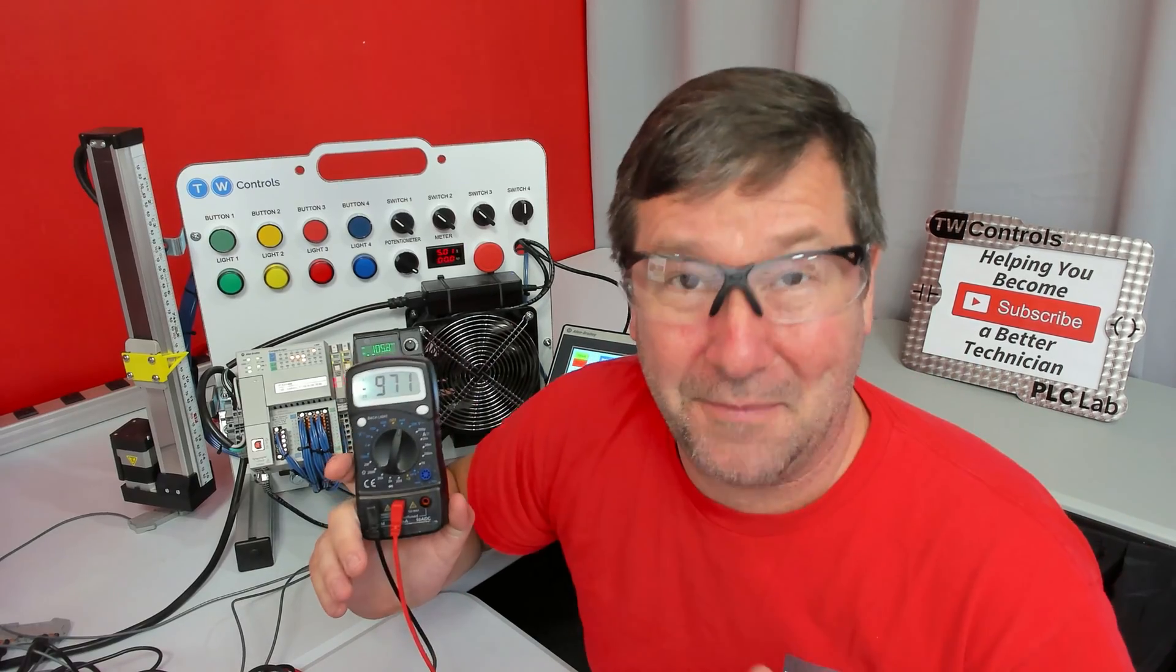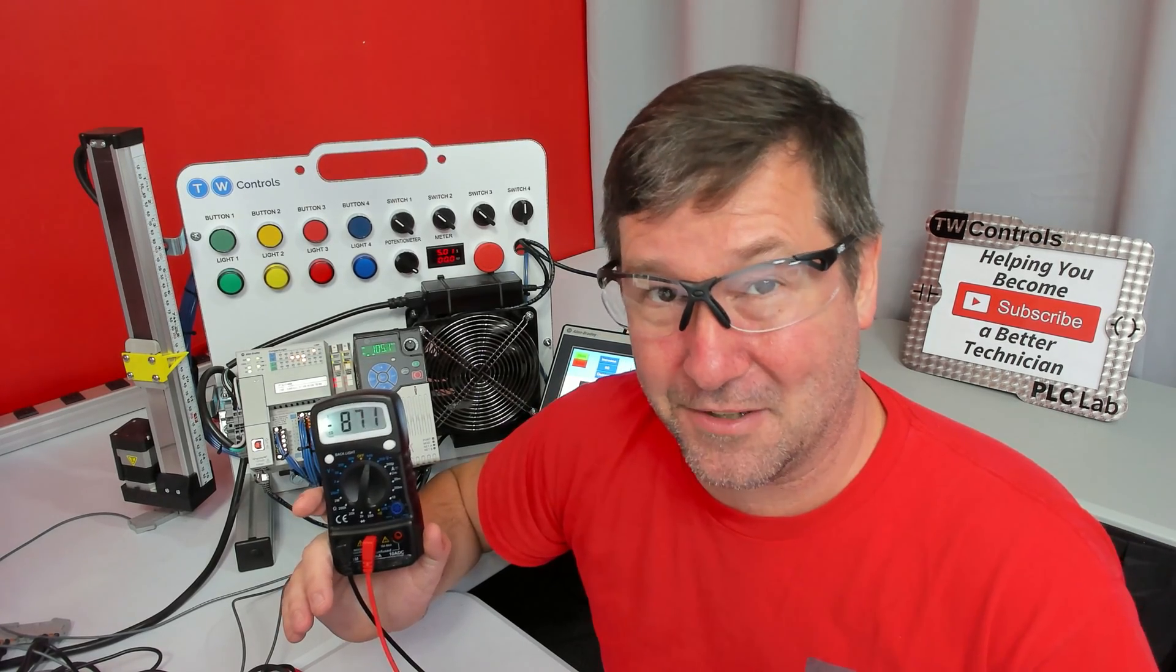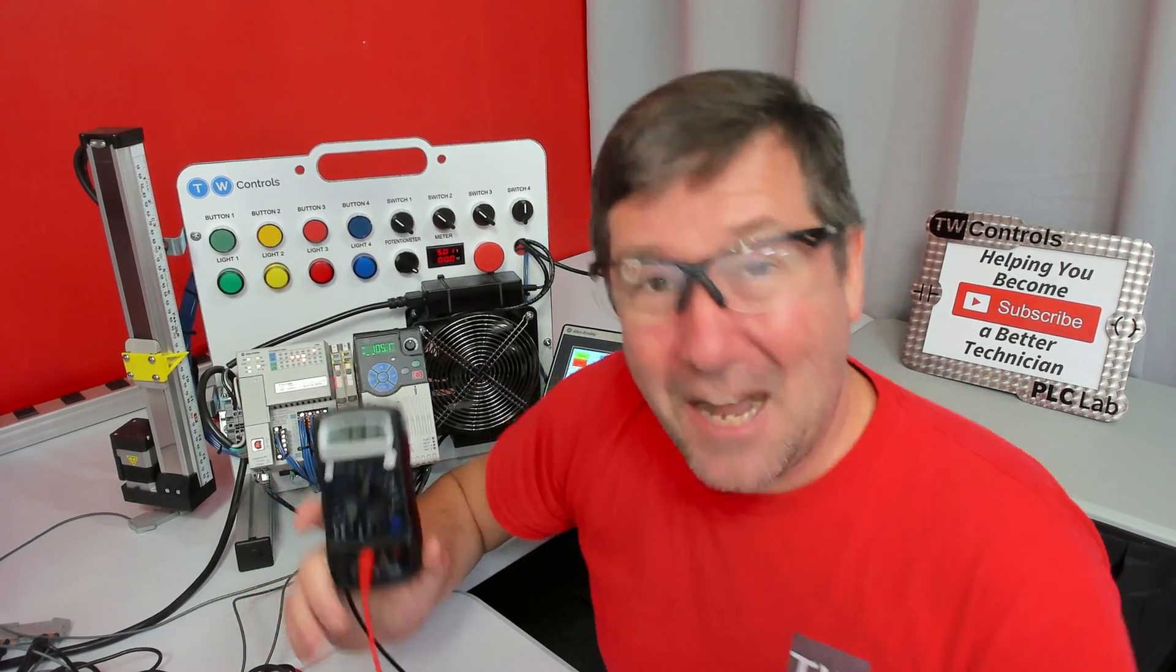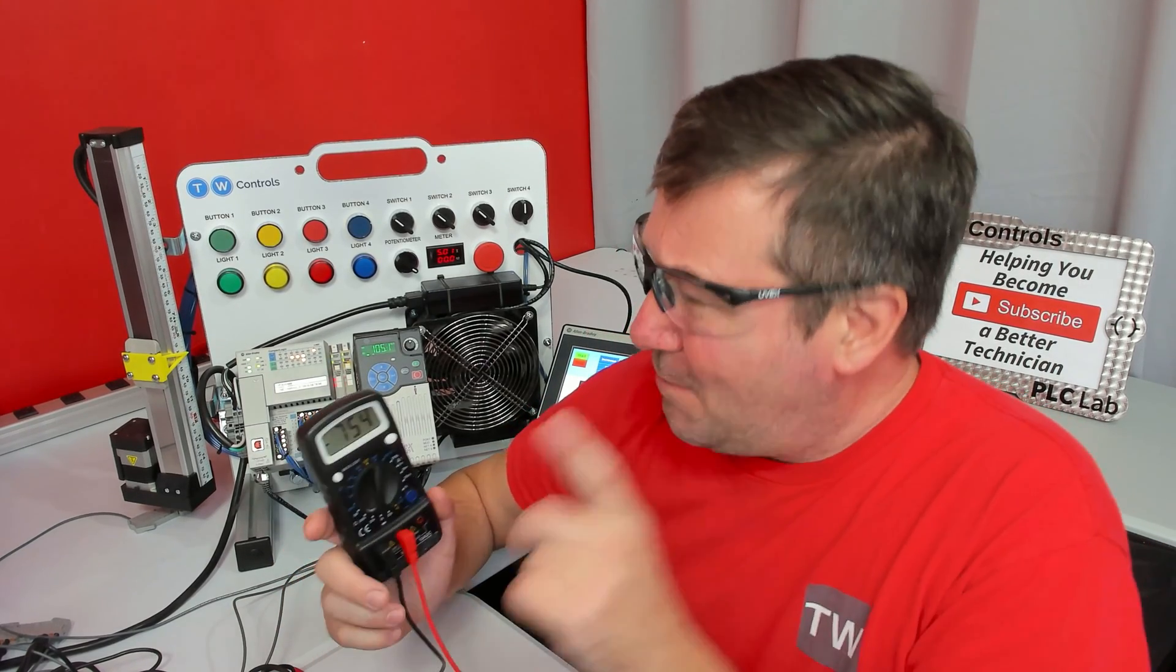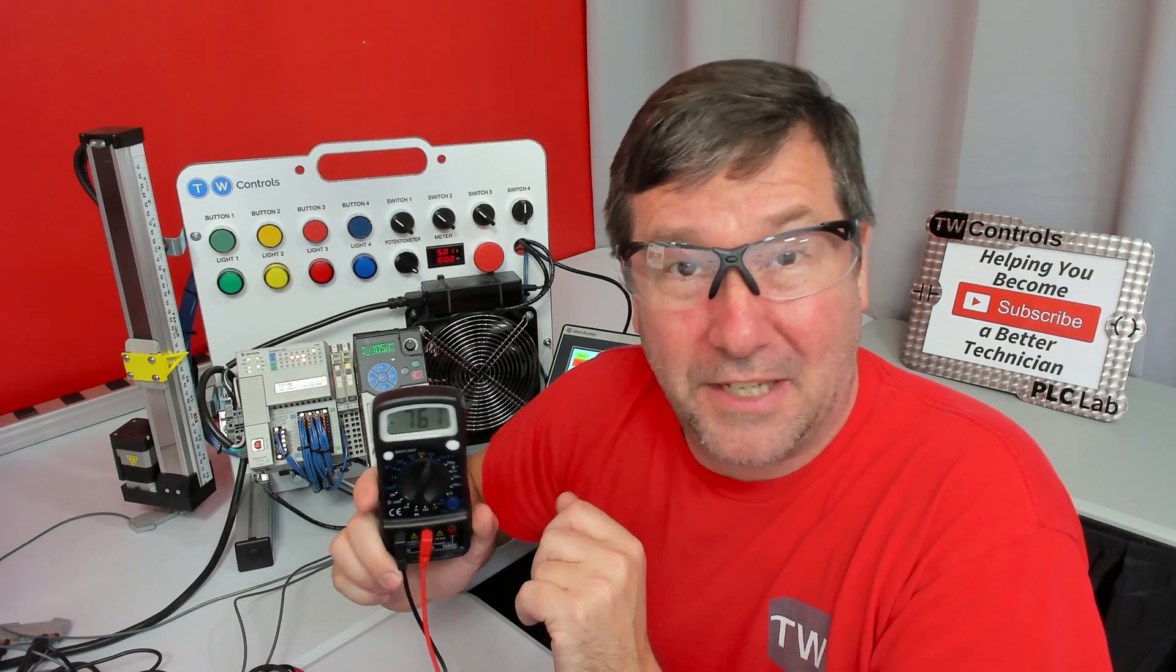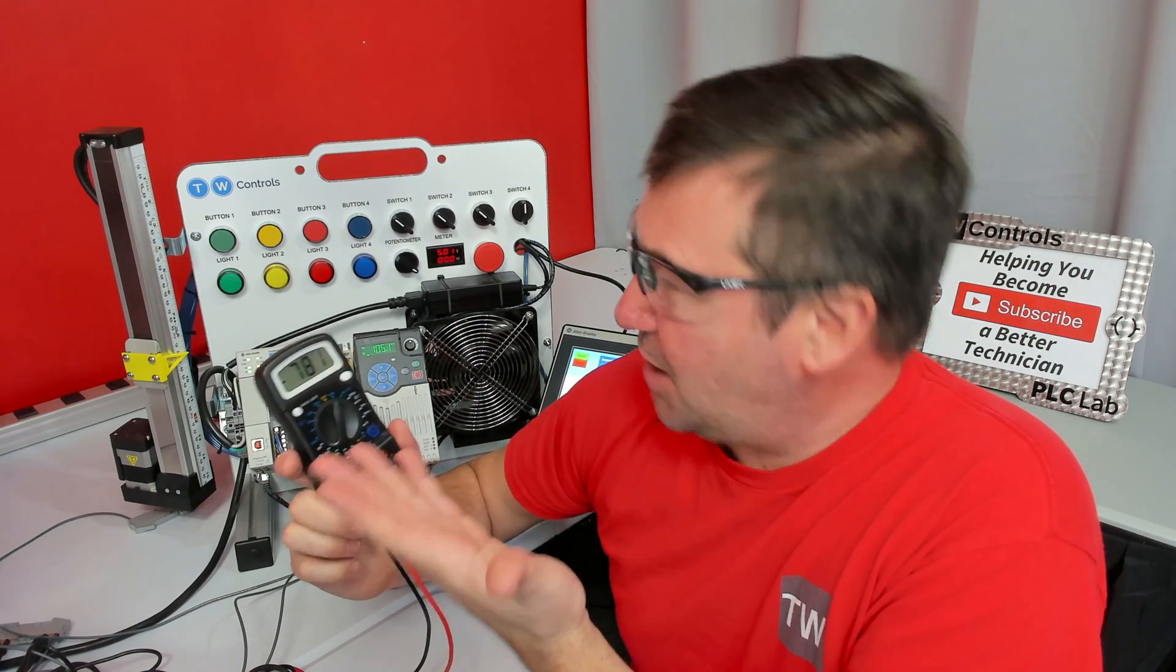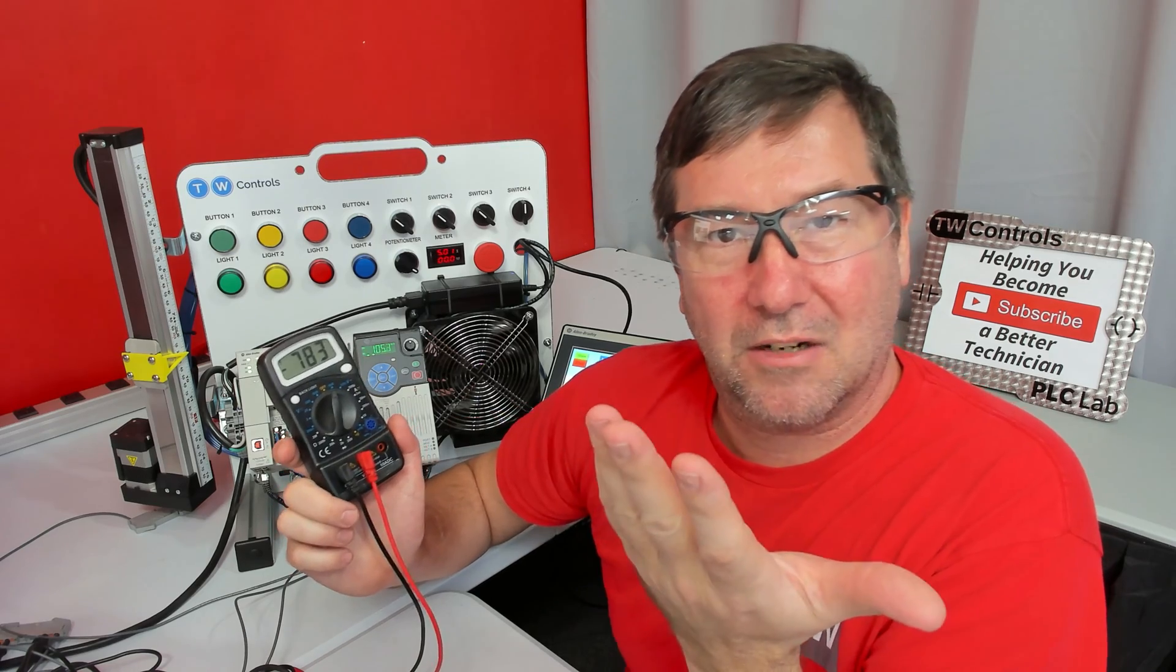This is one of my favorite exercises that I do with my technicians when they come to our training. Now, I'm not going to give you a lot of details on how we end up into this because you may end up being in my class one day. But in the end, they need to take this Brand X meter and check the output of this PowerFlex 525. And they end up showing like 780 volts or something crazy. And they're like, well, there's got to be something wrong with the drive.